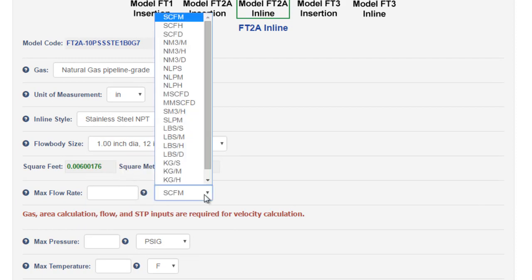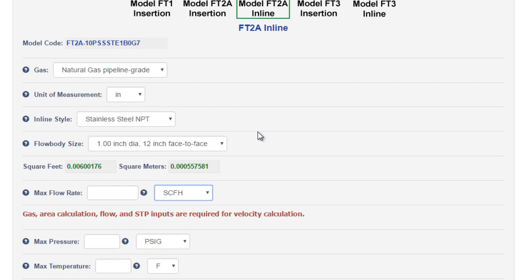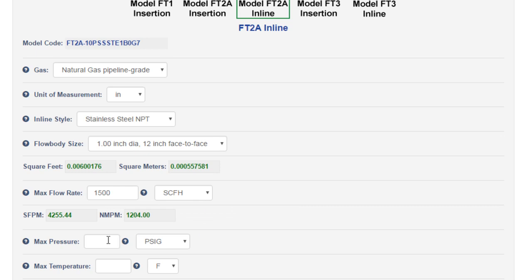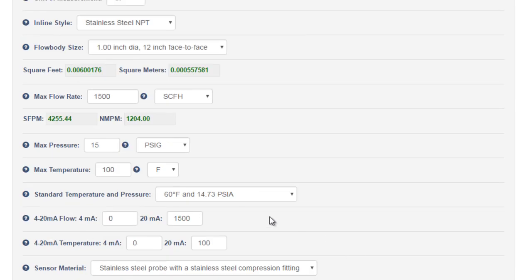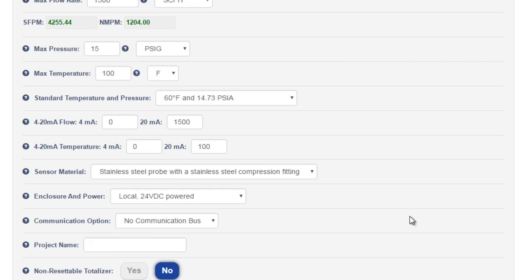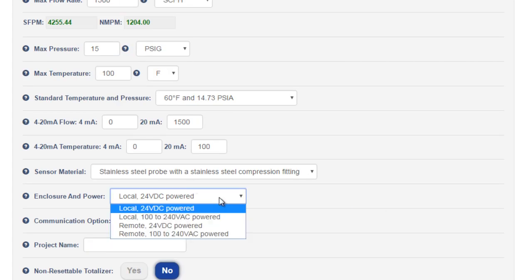We'll change our flow rate to SCFH, standard cubic feet per hour, and enter in a maximum flow rate of 1500. Once again, we'll enter our max pressure and max temp. You'll note here that the STP was defaulted to the 60 degrees Fahrenheit option. This is standard in the US for natural gas. We'll leave the 4 to 20 settings alone. We'll leave the stainless steel probe as it is. We'll go with a remote display this time, 24 volts powered.